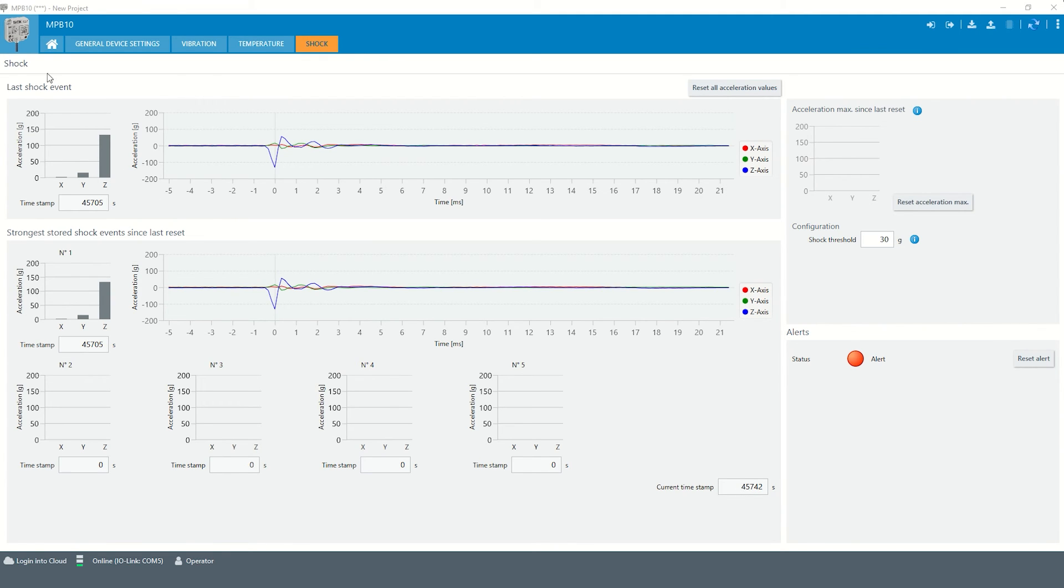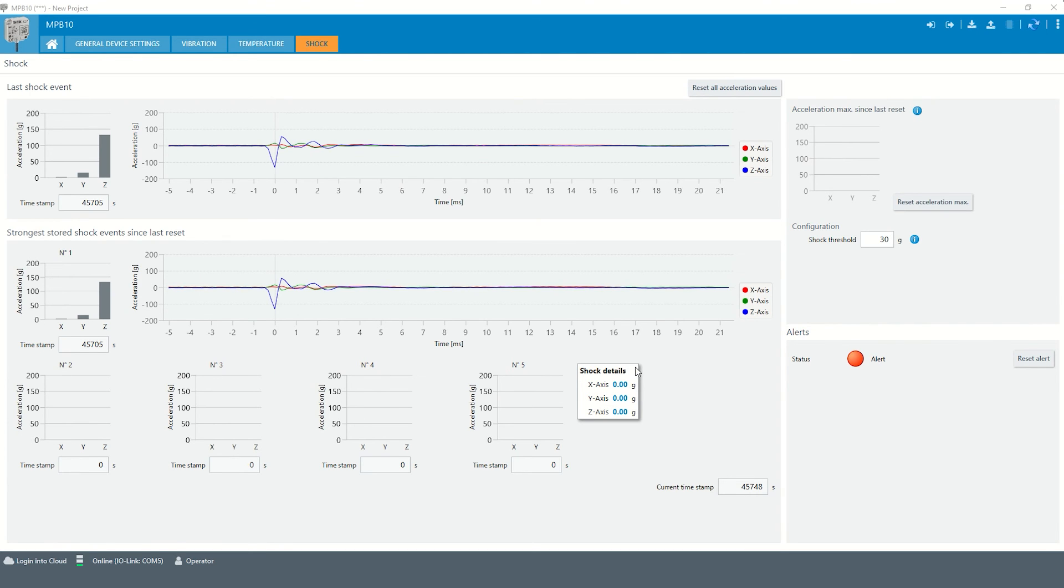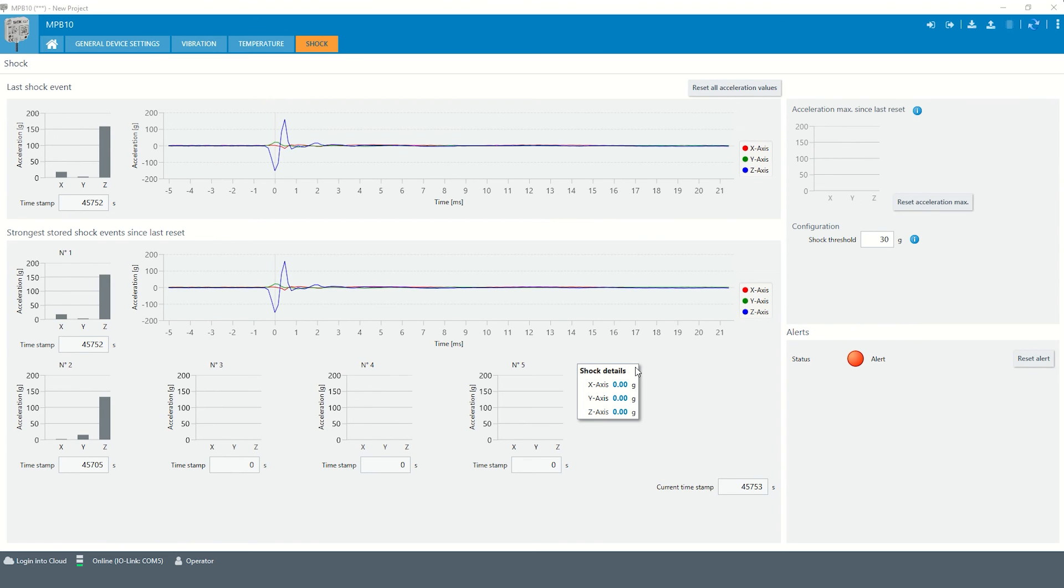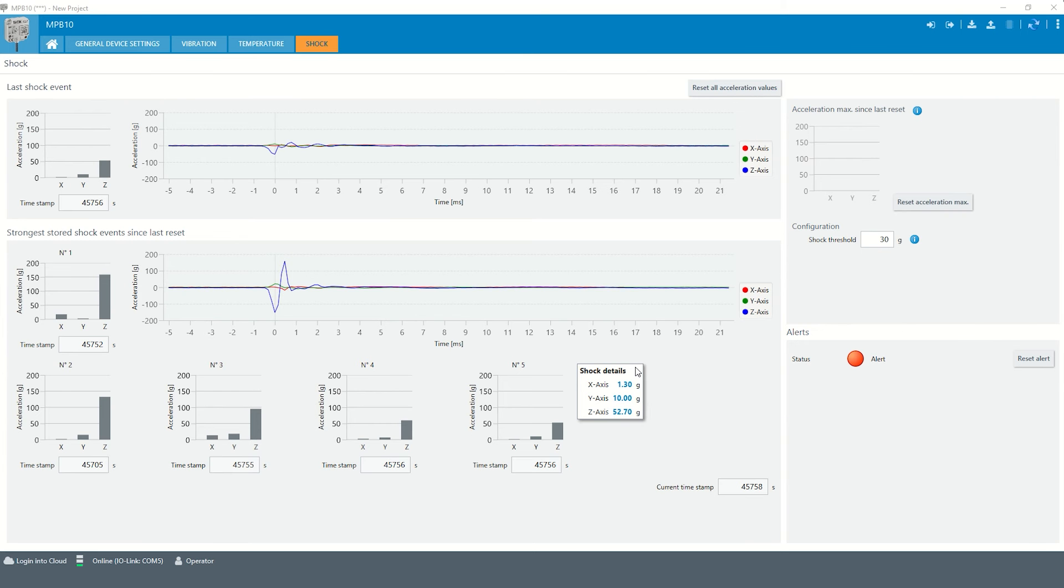Besides the last shock event, the five strongest shock events are stored in the sensor permanently. Each newly added shock event is sorted according to its strength. If a new shock event is added, the shock with the lowest acceleration is overwritten accordingly.